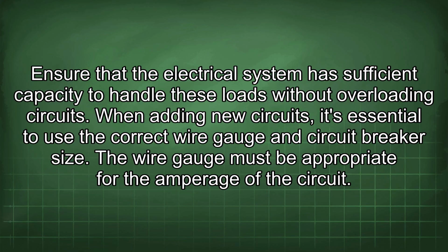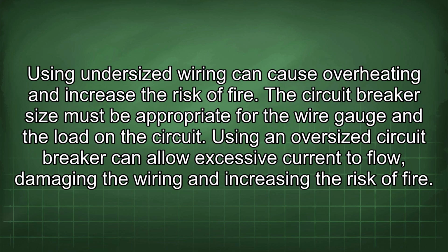When adding new circuits, it's essential to use the correct wire gauge and circuit breaker size. The wire gauge must be appropriate for the amperage of the circuit. Using undersized wiring can cause overheating and increase the risk of fire. The circuit breaker size must be appropriate for the wire gauge and the load on the circuit. Using an oversized circuit breaker can allow excessive current to flow, damaging the wiring and increasing the risk of fire.